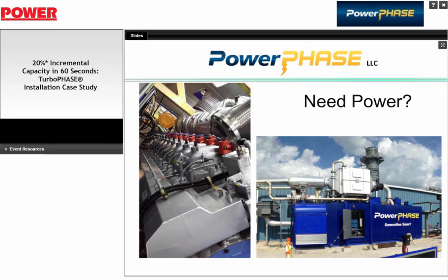But the emissions on the natural gas recip engine, for recip engines, they basically quote it in grams per horsepower hour. That's how the federal regulation, subpart 4J, defines the emissions regulations for the recip engines, natural gas. And this engine actually can operate, and is operating here at Morris, at basically half that level. So the emissions rule is 1 gram per horsepower hour, and we're operating at a half a gram per horsepower hour, which, when you look at it in terms of gas turbine emissions, is on the order of 40 ppm.